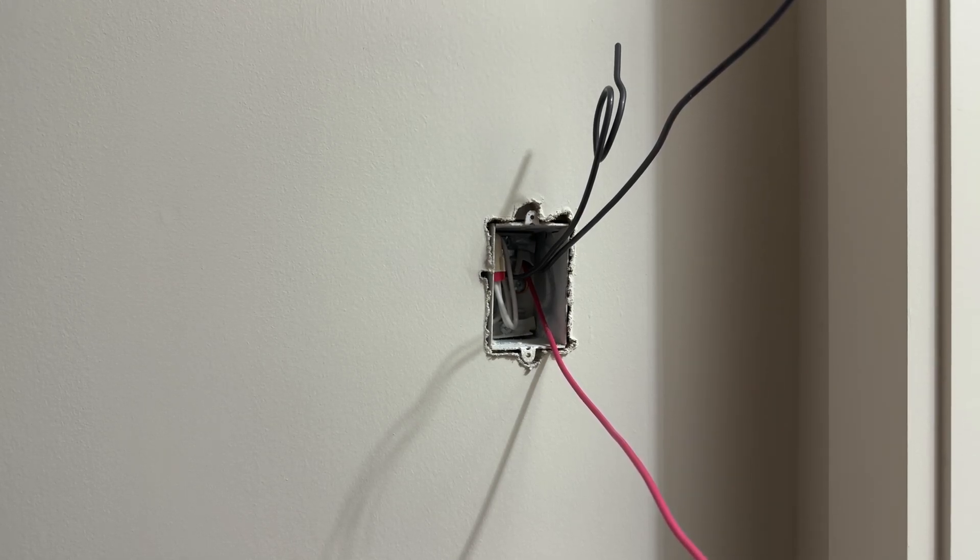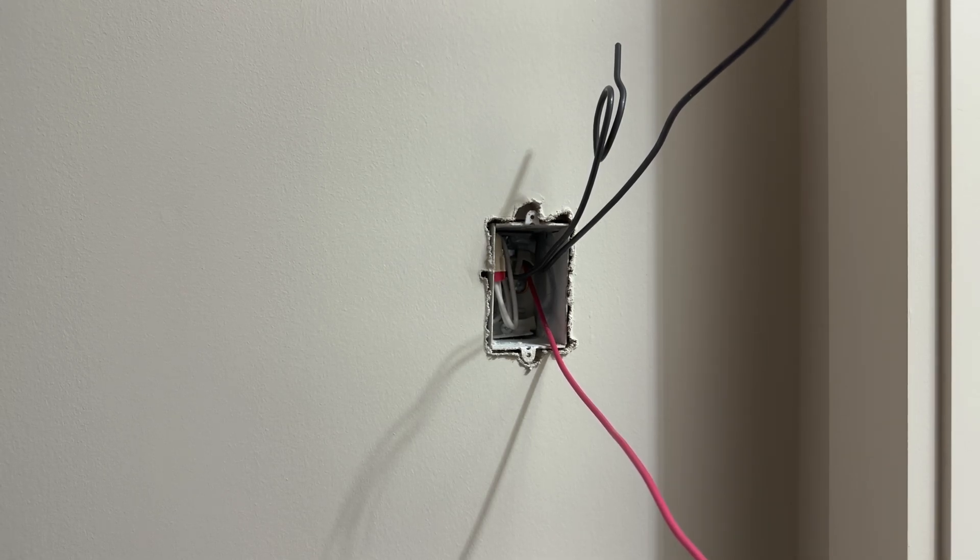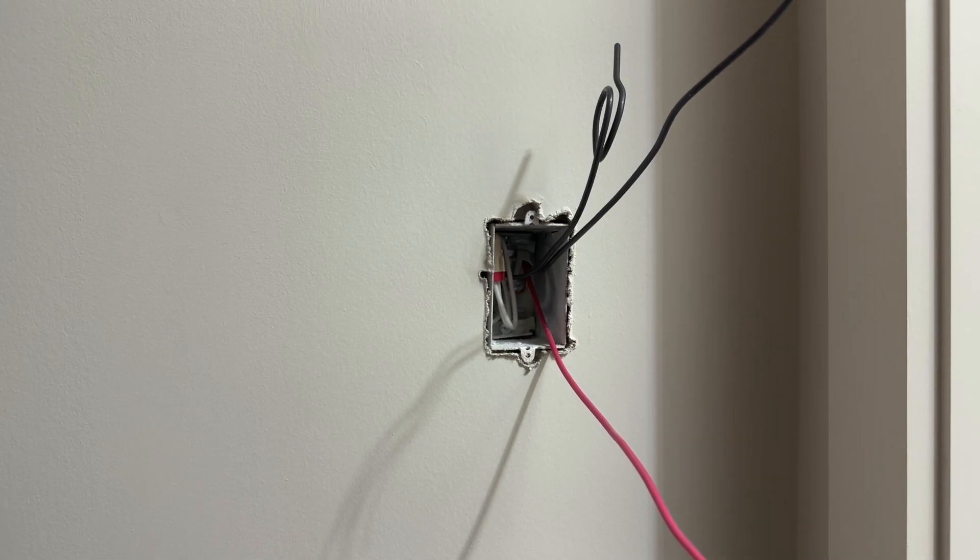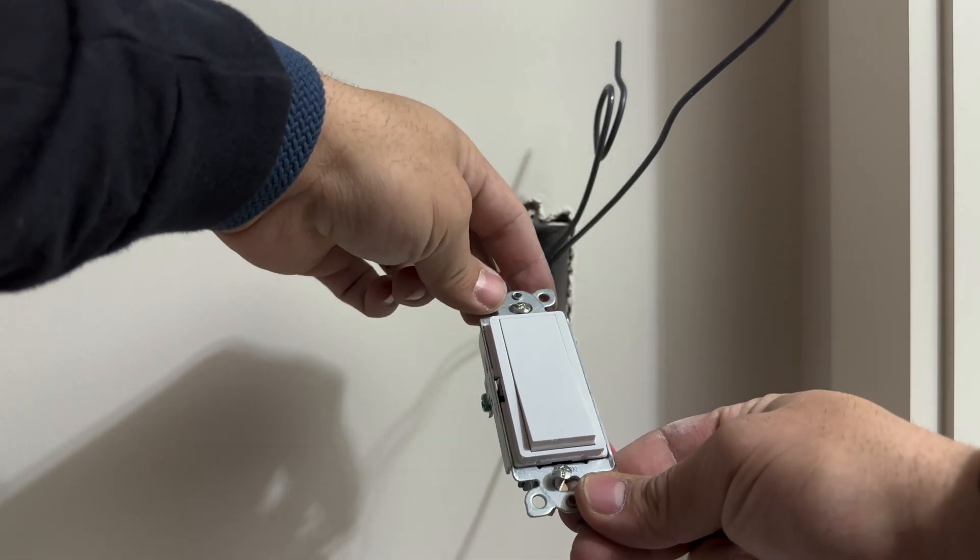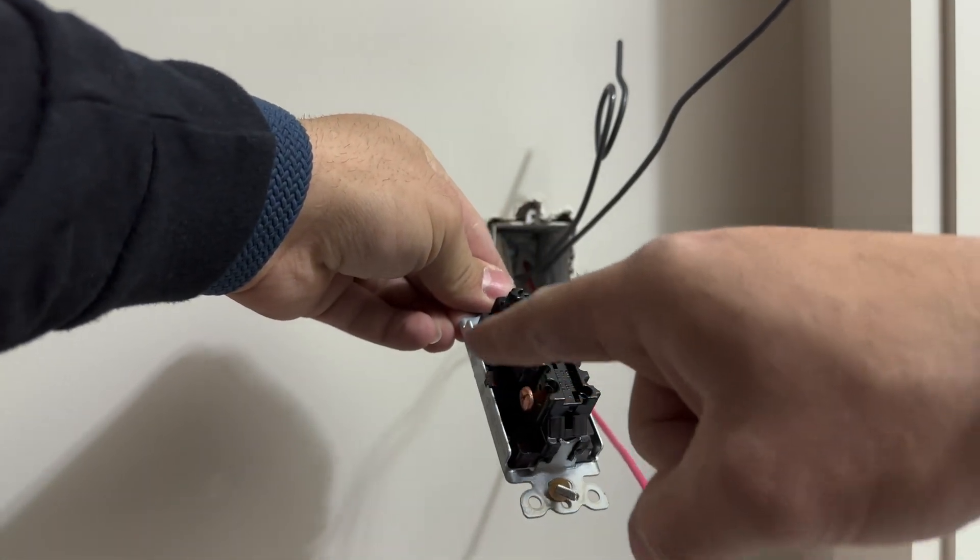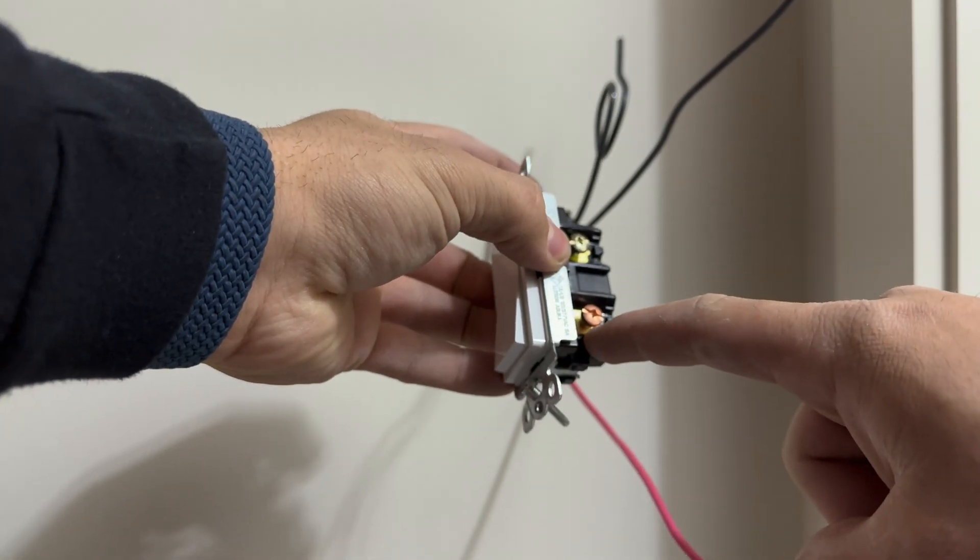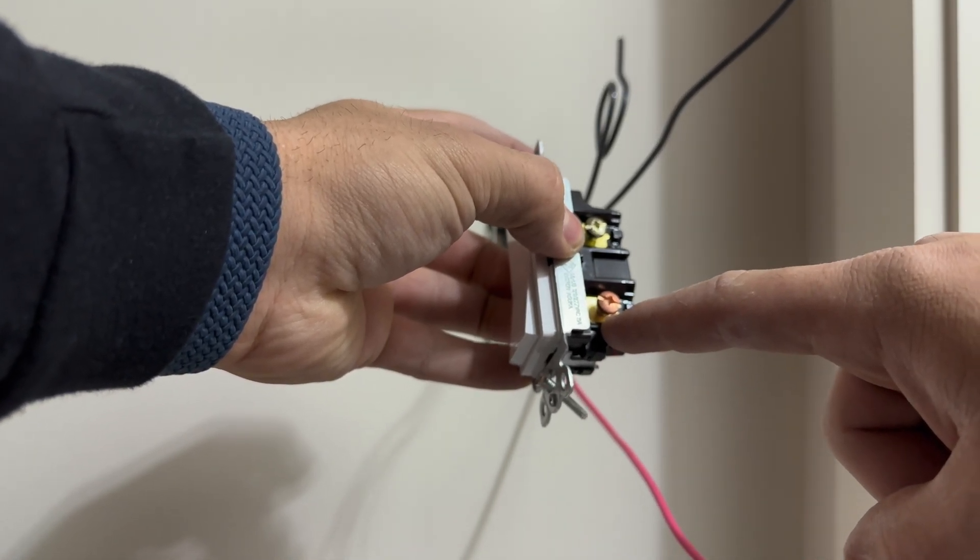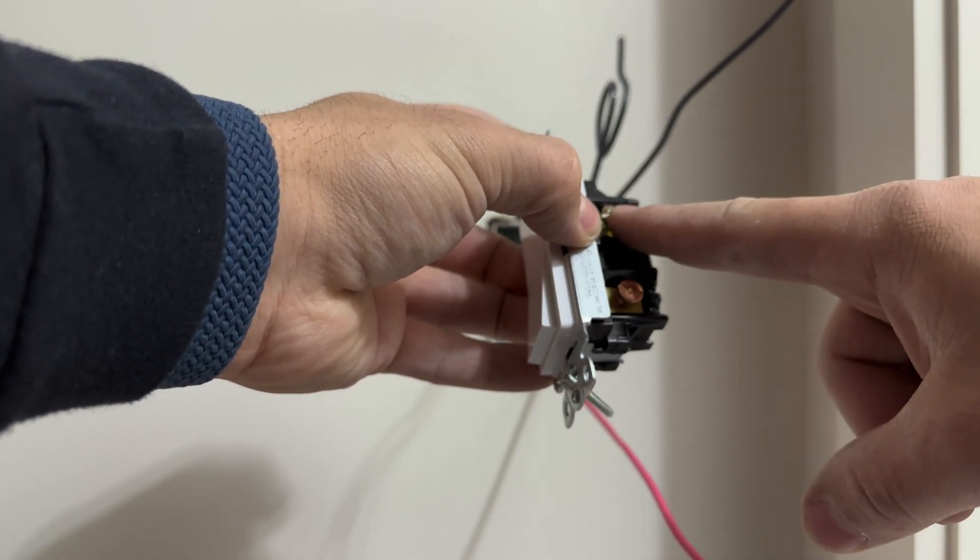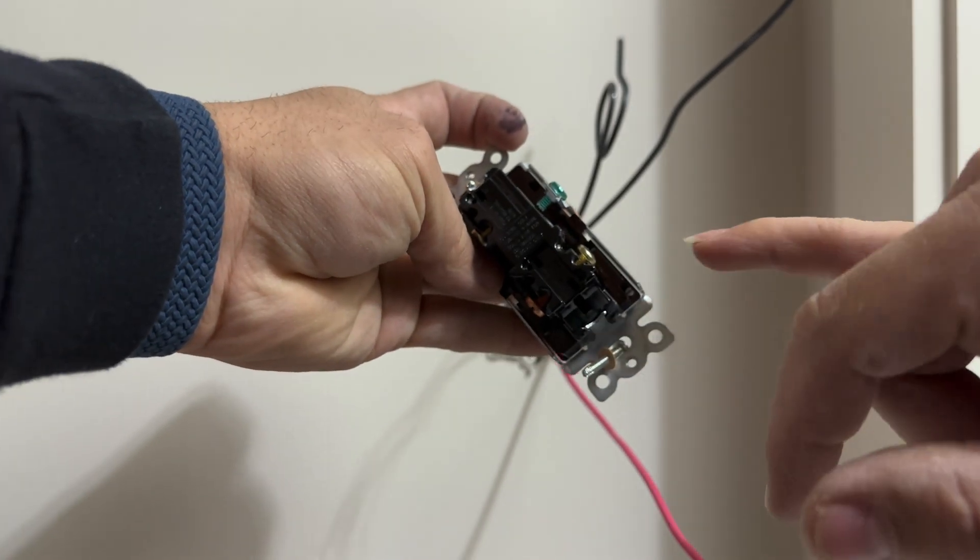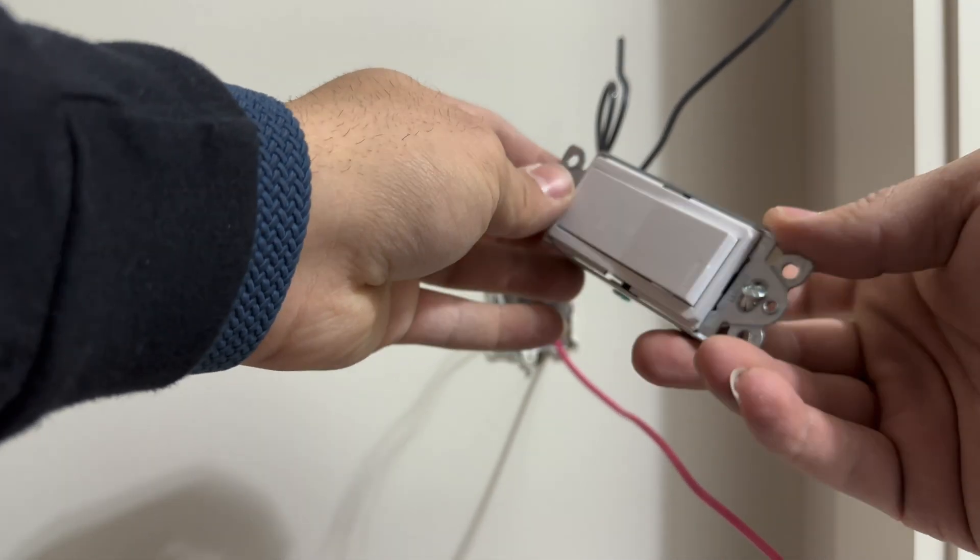So right now if you've never seen a three-way switch, please allow me to show you how it works. A three-way switch unlike a single pole switch has three connection screws plus a ground screw. So the copper looking screw will be your common. This will be your power and this will be your traveler, the communication wire between the switches.